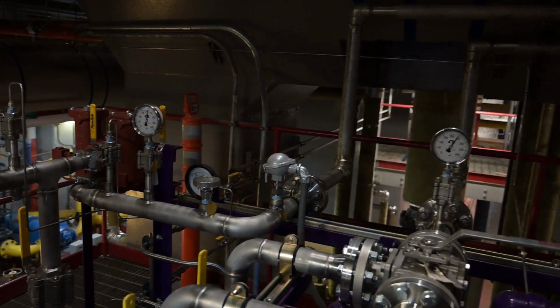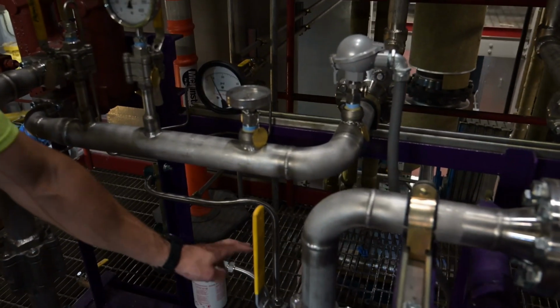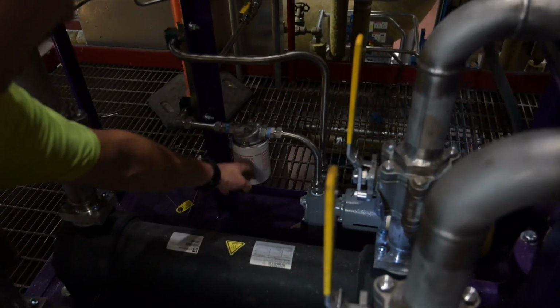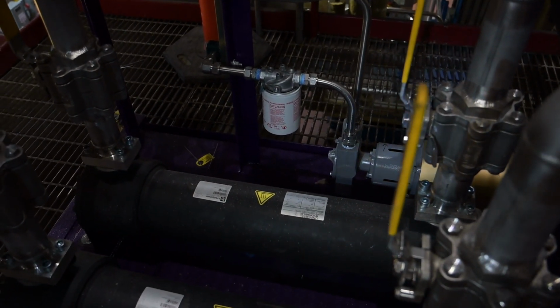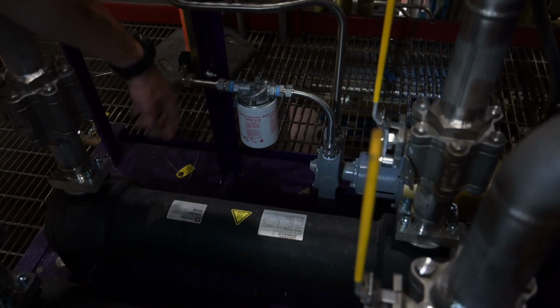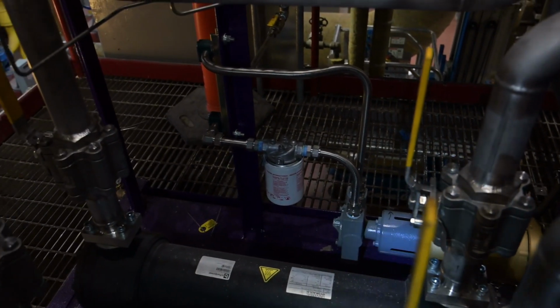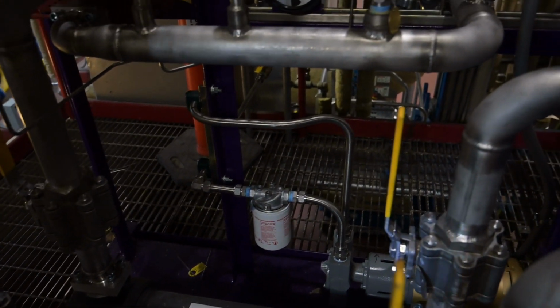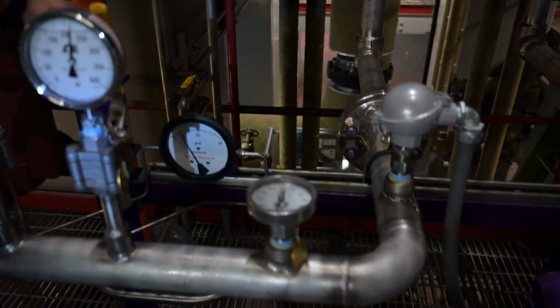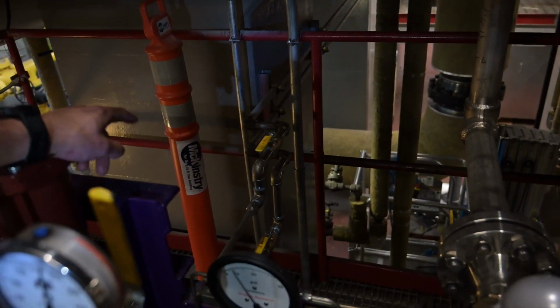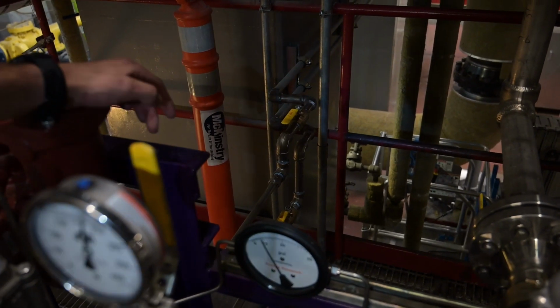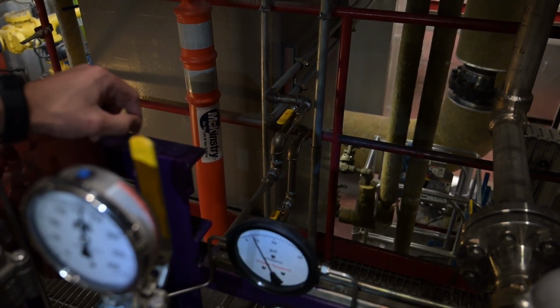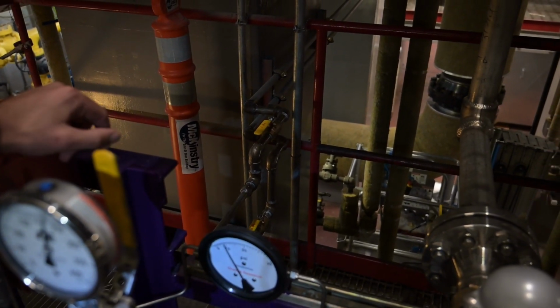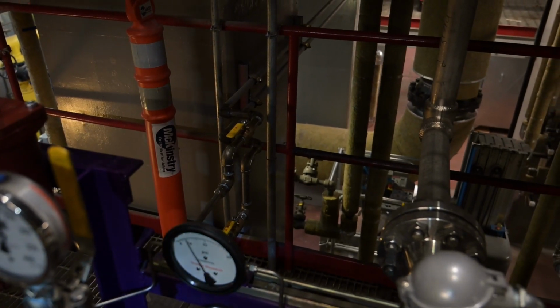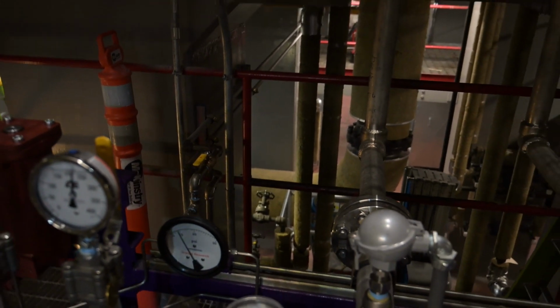We've also got the emergency oil pump back over here with a filter. So that is suction, this is discharge. We also have isolation valves over there. We had to add those in because the emergency oil pump is down below the turbine and there's no isolation valves up top. So in order to change the filter, you'll need to close off the isolation valves.